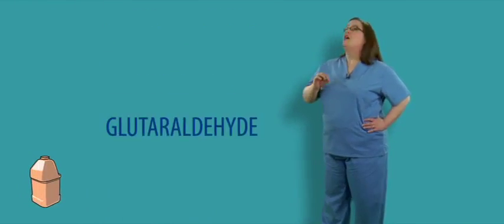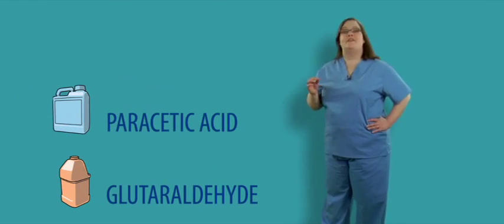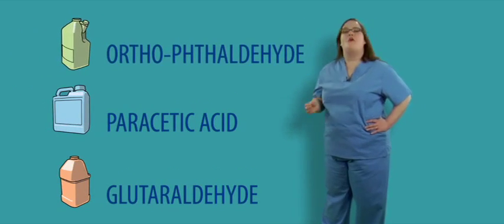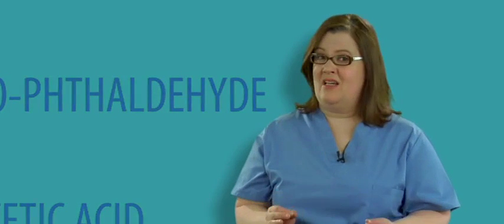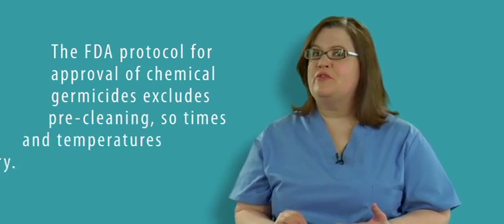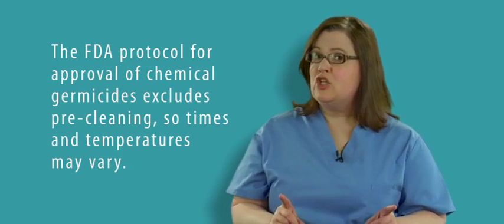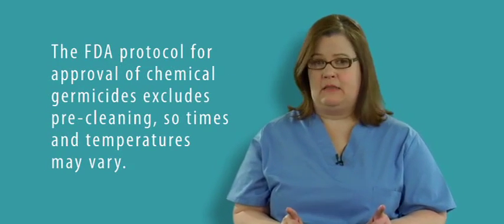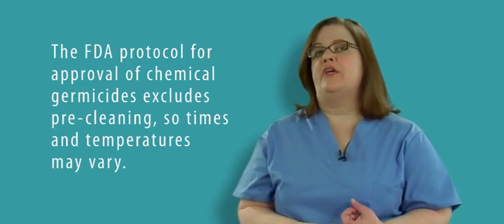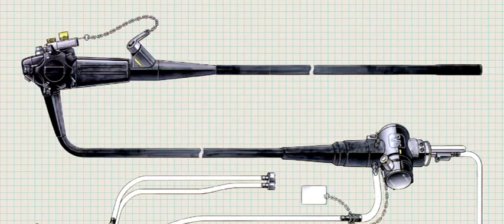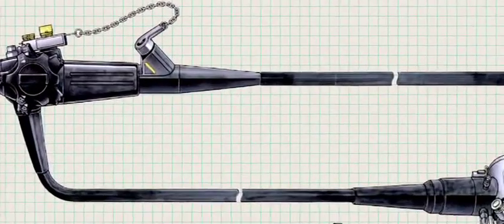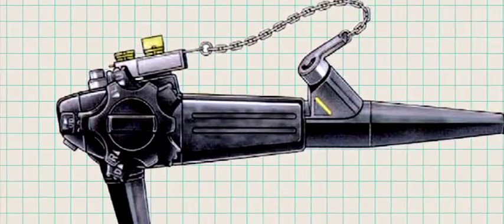Only chemical germicides cleared by the FDA as high-level disinfectants and sterilants should be used for high-level disinfection. For example, a glutaraldehyde, peracetic acid, and orthophthalaldehyde. Because the FDA protocol for approval of chemical germicides does not include pre-cleaning as part of the testing, times and temperatures may vary. By the nature of their design features, endoscopes are more difficult to reprocess than other medical instruments.